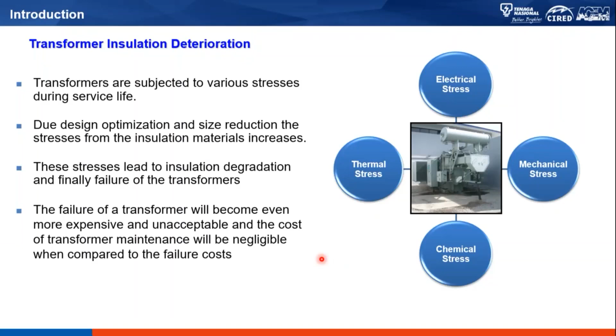We have here the interturn short on the LV windings, as you can see in the photo here. And then on this one here, it's a large transformer actually. This is a transmission transformer, with the HV yellow phase winding shorted. And this is what we categorize as electrical stresses.